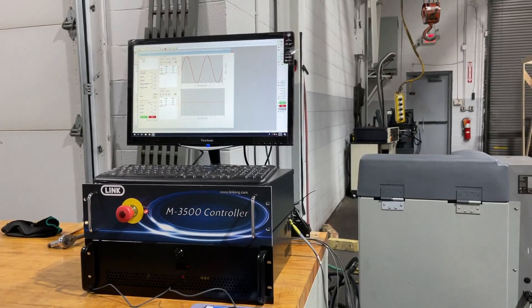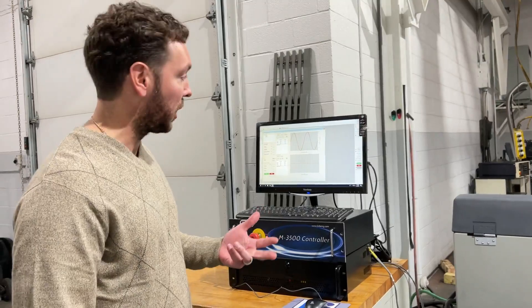And then over here, we have our M3500 servo controller which is controlling all aspects of the frame, whether it's static tensile, compression, or high cycle or low cycle fatigue. This system can do it all.